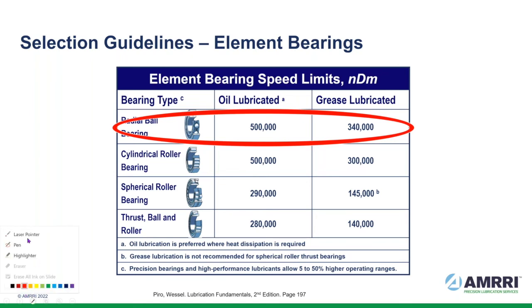It represents the fact that the bearing needs to have oil versus grease in order to operate for the 30 years that the bearing manufacturer says it should operate. Even if you're force feeding grease, those applications ought to be evaluated for a change from grease to oil. Just moving from a grease bearing to an oil bath would be a big improvement. Moving from a grease bearing to either mist or air over oil would be a better improvement. But the bottom line is we need to make sure that what we have in place is an acceptable technical fit prior to making a redesign decision.